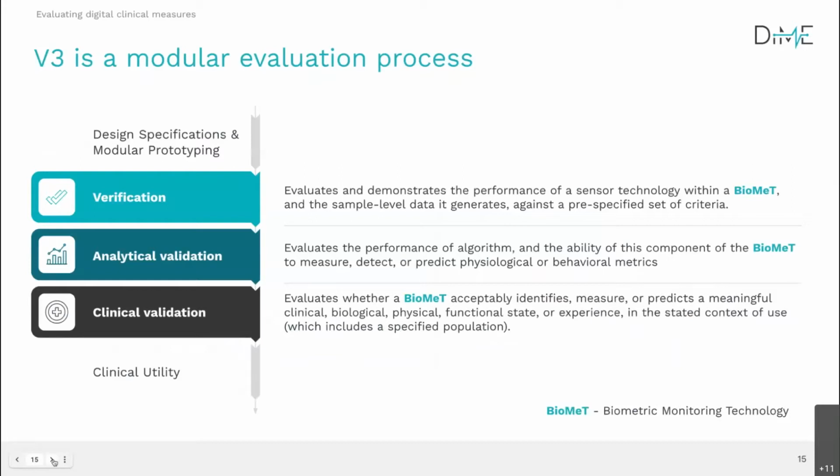Verification describes the engineering testing that goes on to demonstrate that the performance meets the specification standards of your measure. Analytical validation looks at the algorithm that's taking that lightly processed data from the technology and manipulating it into clinically informative data. Clinical validation, a process that I'm absolutely certain everyone on this line is very familiar with, is the process of proving that this measure is relevant, valuable, things like minimum clinically meaningful change.